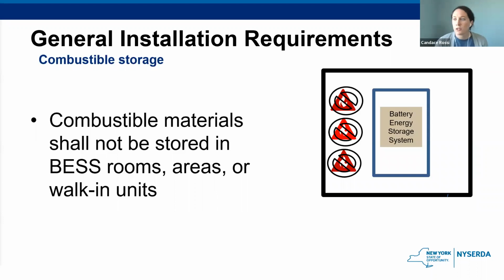So continuing with general installation requirements, I think once again, this is a pretty common sense requirement. Any combustible material should not be located within 3 feet of cabinets containing the energy storage system or within a walk-in unit or room. Having a fire on the exterior of the system could possibly cause the batteries to fail and lead to a fire in the storage system. So usually a best bet to avoid any potential fires close to a storage system and just ensure that if there is any combustible materials, that they're just not stored close to energy storage.